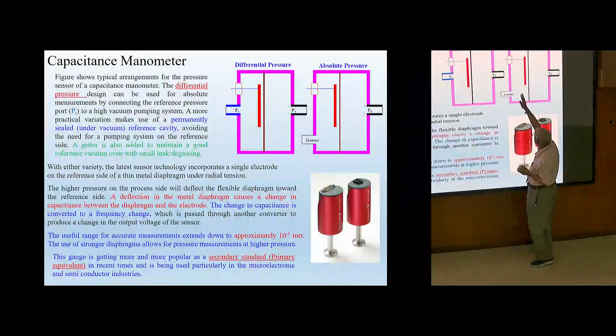there is a metallic diaphragm, there is an electrode, and the gap between them gives epsilon naught A by D; this is the capacitor. This is insulated so that it is not short circuited with the body. This is the gauge. This is connected to the chamber to be measured, the vacuum. Now as the vacuum is developed here, this is closed, and a getter, a small pump, is used as a chemical absorber to take care of any leaks, so that it is always maintained at 10 power minus 7 torr. This side is at minus 7 torr. This other side is connected to the chamber.